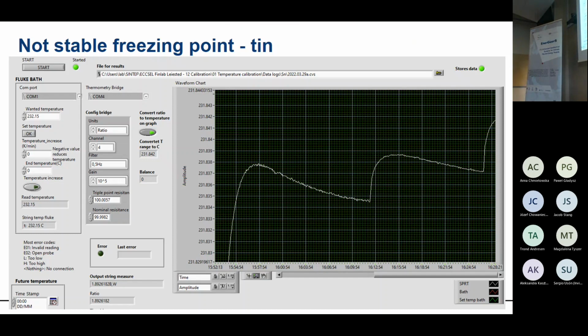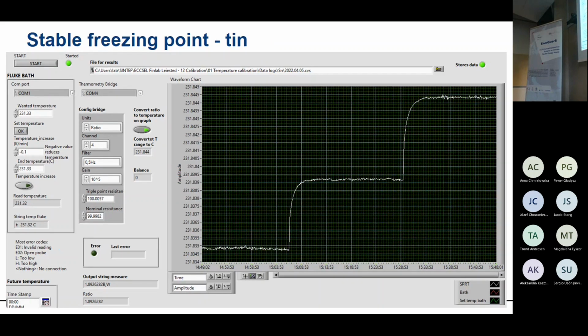Here is the screenshot from the logging program and the not stable freezing point. We are looking for the plateau. And the plateau is this state. We have the very, very stable freezing temperature. And you can ask what these jumps are. These are the jumps of the current, because here the current that was flown was 0.5 milliampere, here was 1 milliampere, and here 1.31 milliampere. And we want to avoid self-heating, so after the calibration we have to extrapolate it to 0 milliampere to read the proper temperature.